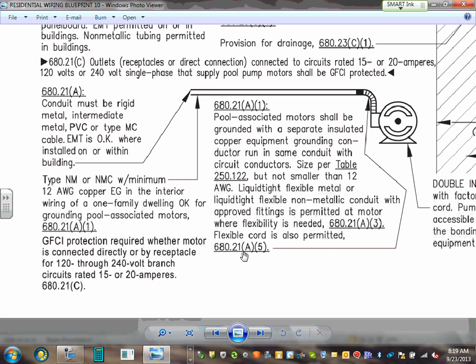If your pump is running at 120 all the way through 240, 15 and 20 amp, they require you to have GFCI, exactly like the pumps that you guys will be wiring. They're running at 240, the pump for a swimming pool. You're required to put GFCI on it. How do you put a GFCI on a 220? Circuit breaker. So the circuit breaker that you feed to the pump has to be GFCI.